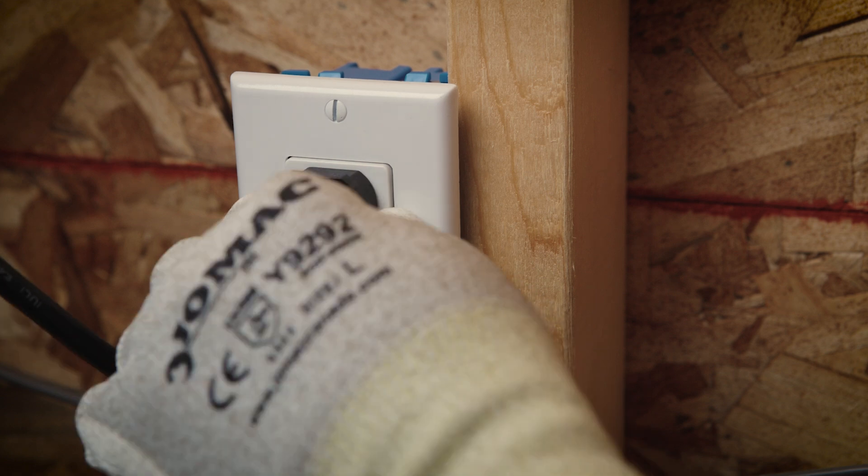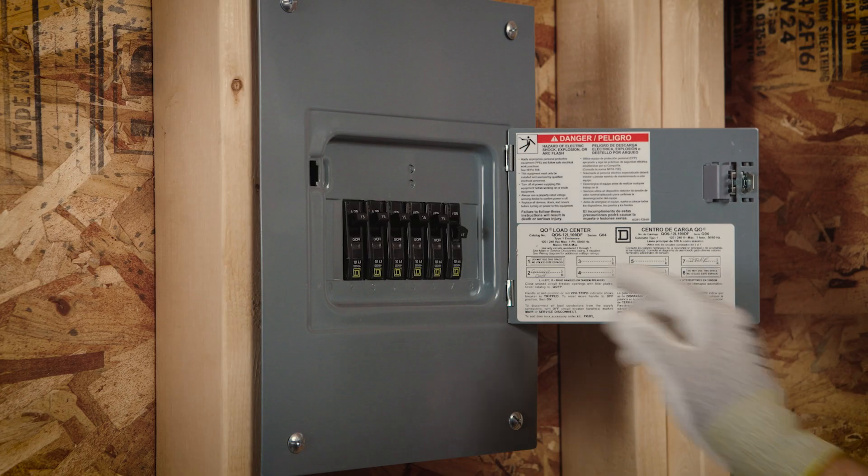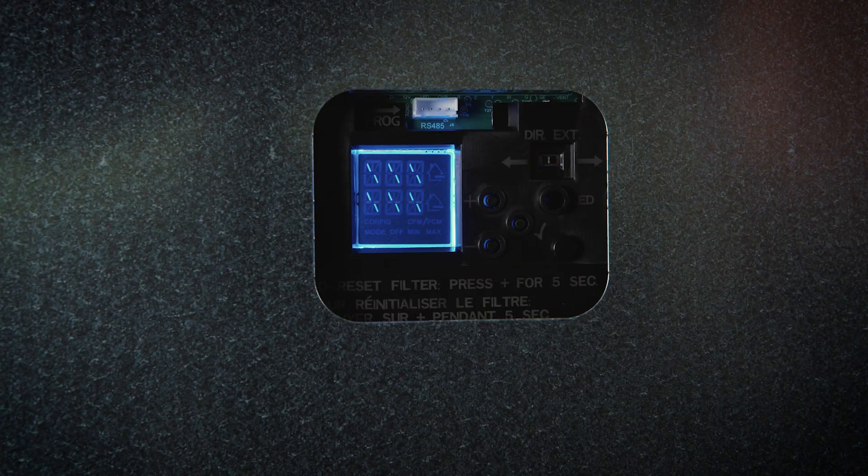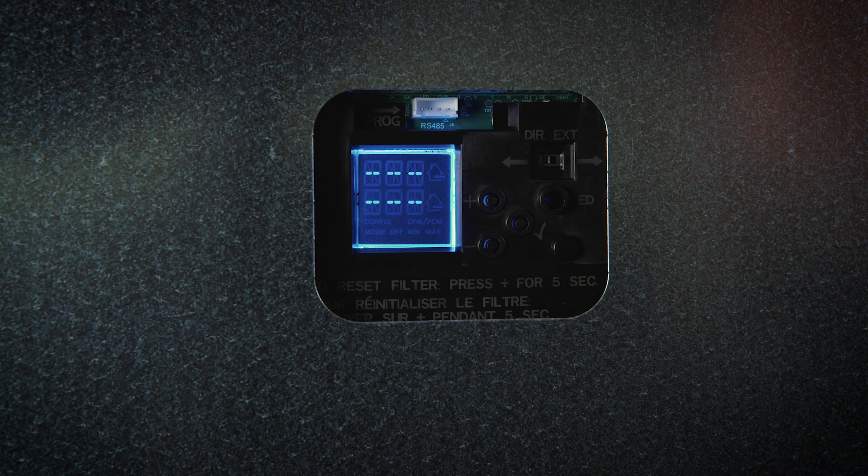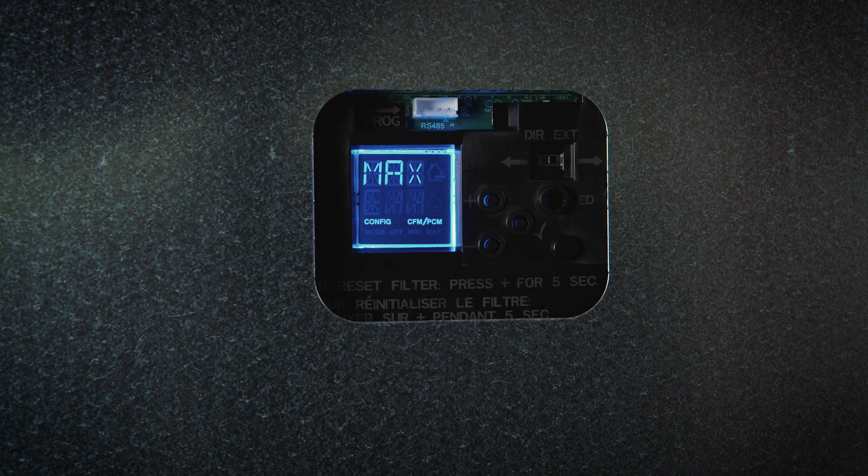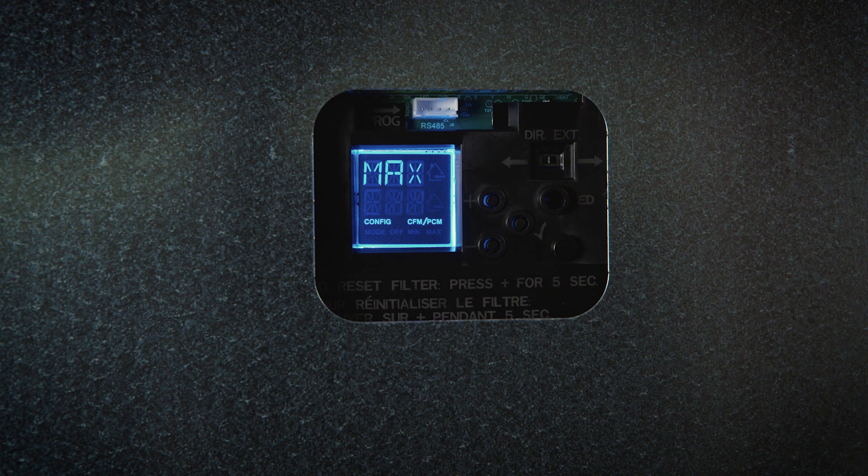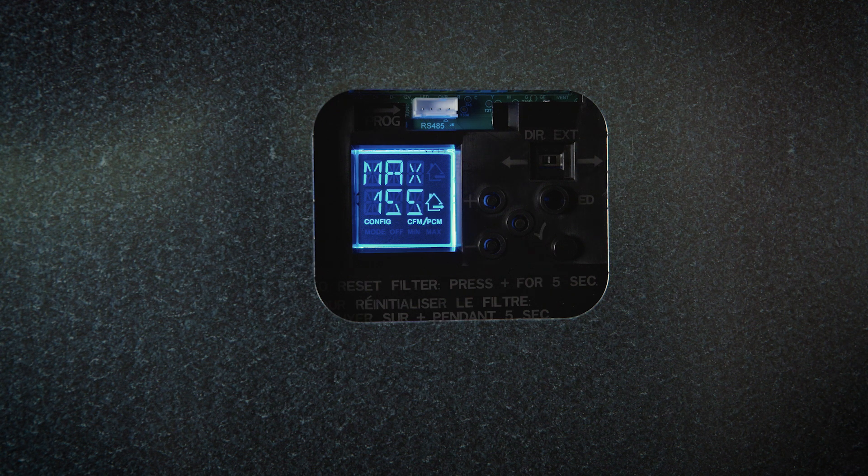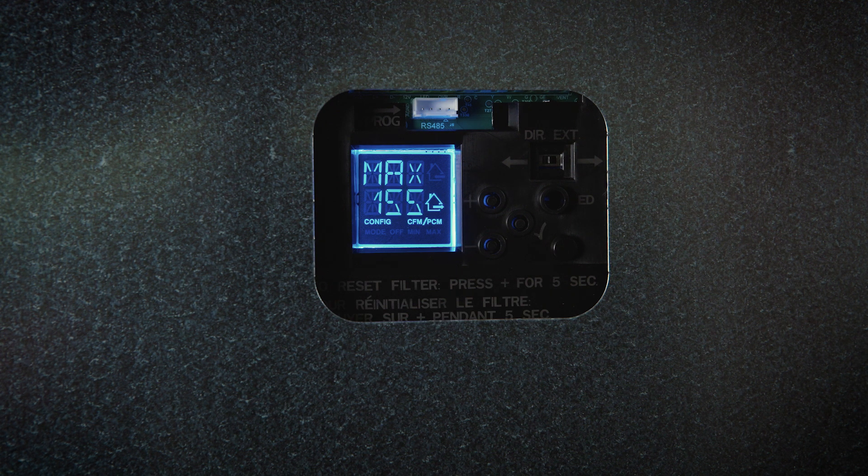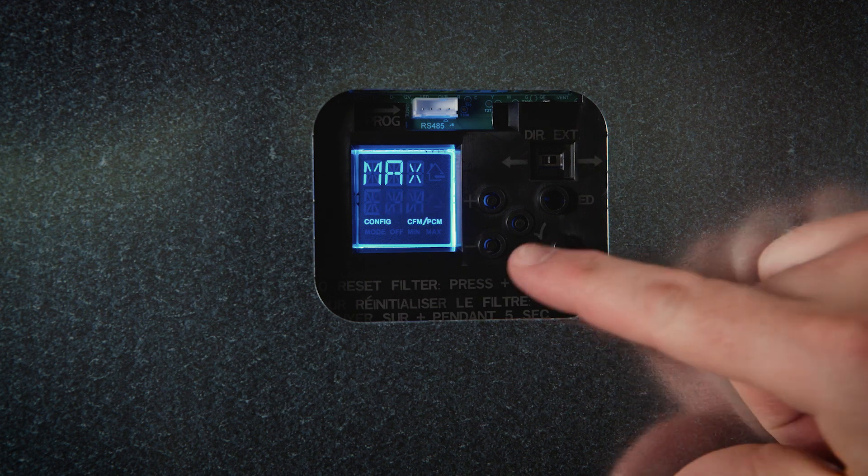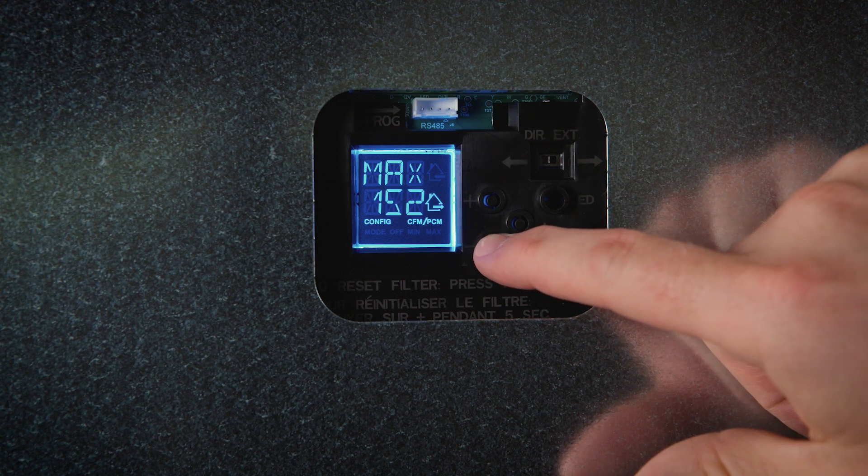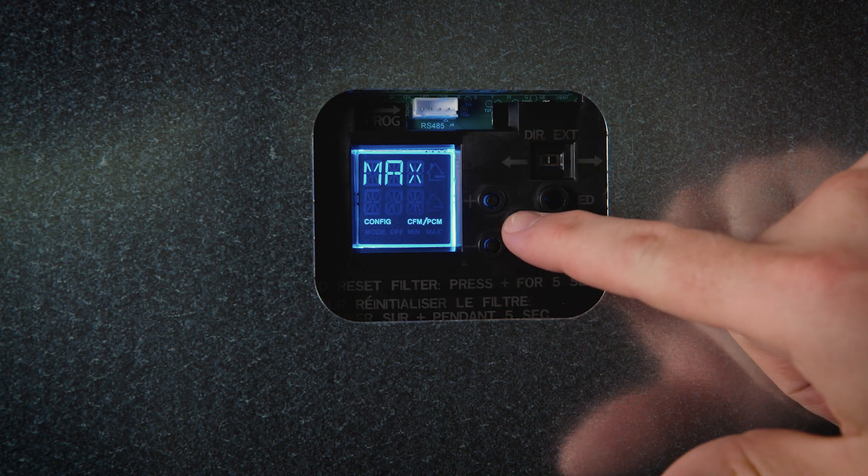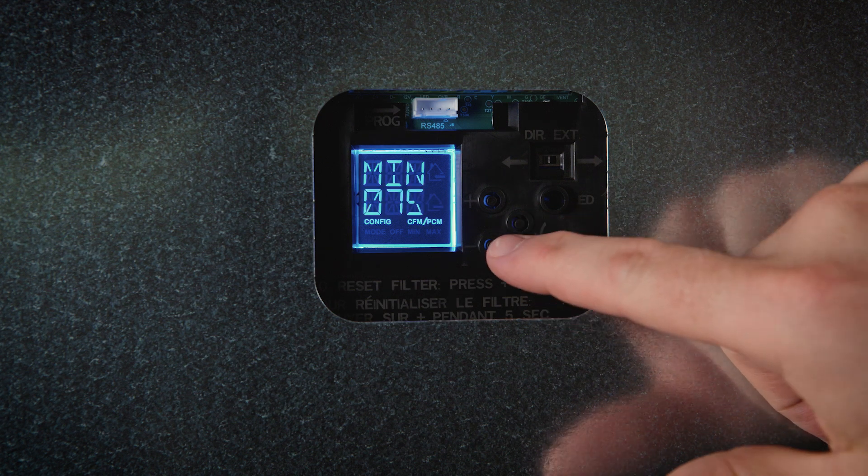Plug the unit into an electrical outlet or turn power on at electrical panel and let Virtuo verify the airflows at initial setting. In a few seconds, Virtuo will display the maximum airflow value and either the house supply or exhaust icon will appear to indicate which airflow is more restricted on the LCD screen. You can use the plus or minus buttons to adjust the desired maximum value and press the check mark to confirm.